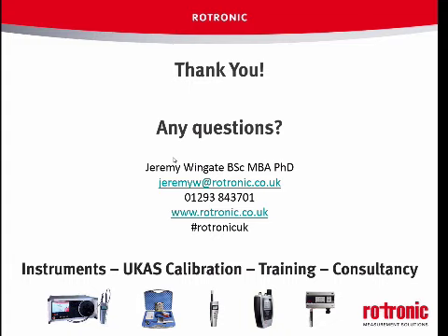And if you're buying a £50 sensor with probably 3% accuracy and 2 or 3% drift over a year, it could be wildly different. Interesting area. It's one I read about some years ago, where they put a number of these in a test cell, US Army, and found they drifted. The difference was enormous. But there's an ASHRAE research project that Chris has just told me about, so we'll pass that on to you, Jeremy. Fantastic. Okay, we've probably got time for just one or maybe two questions if we're really swift.